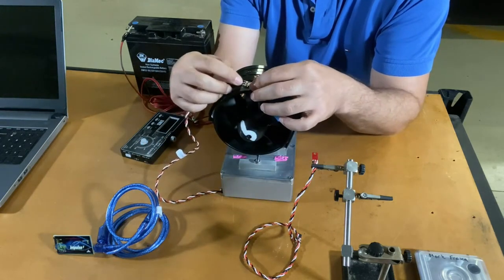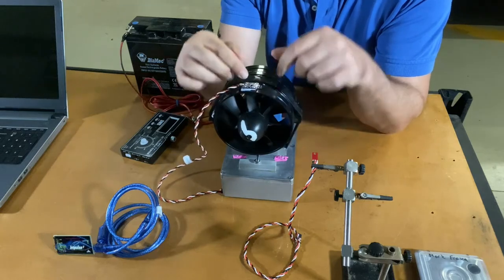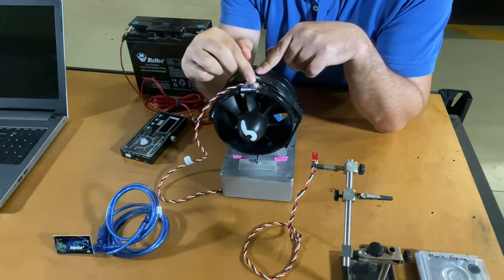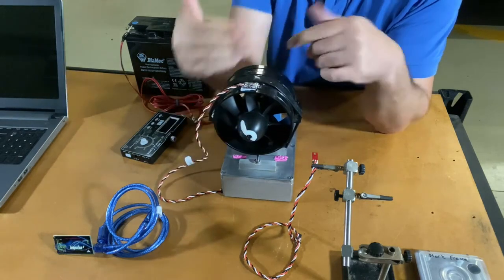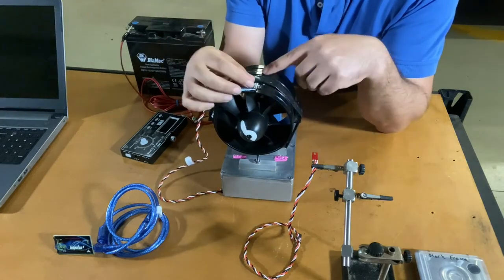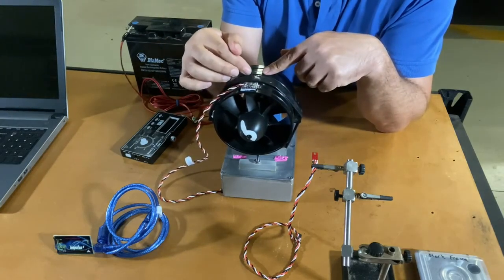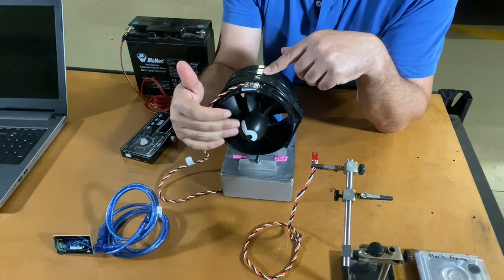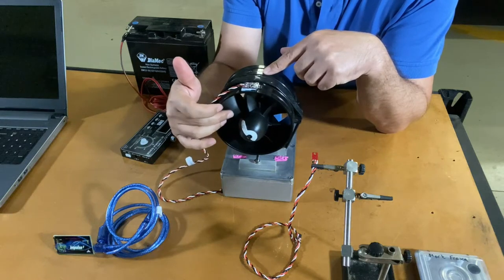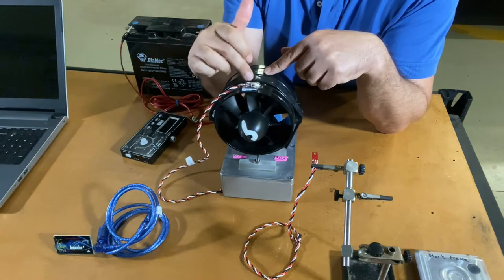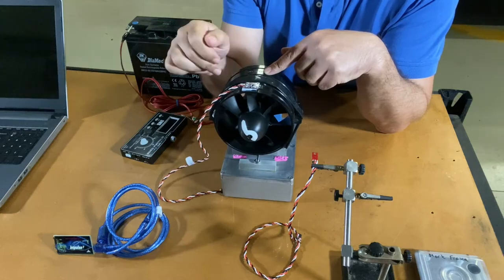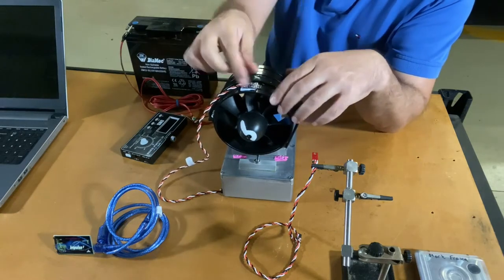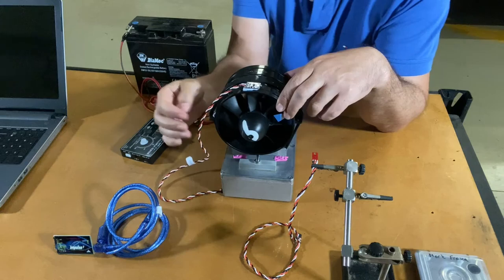Now I'll mount that on top there. Now ideally we would want to mount the sensor directly above the plane of the impeller, so that the maximum vibration or unbalance from the impeller is transmitted directly in line with the accelerometer. So that's mounted on top of the impeller.